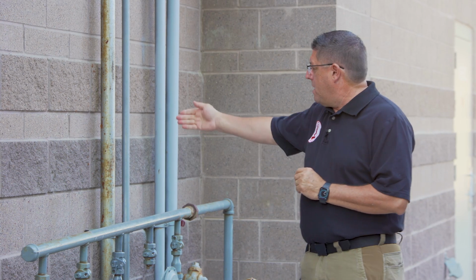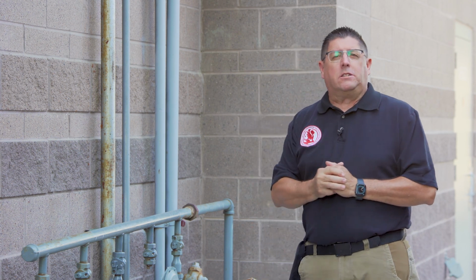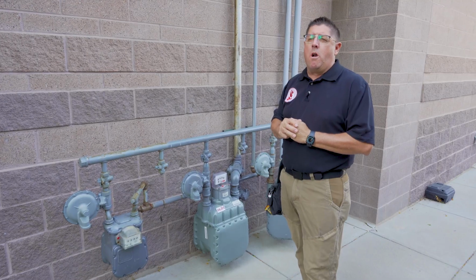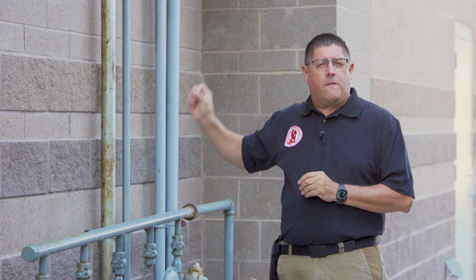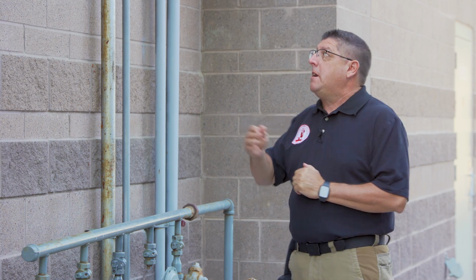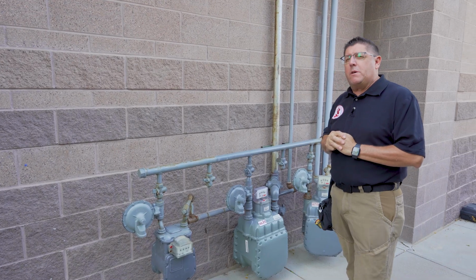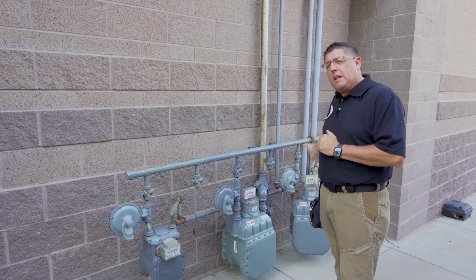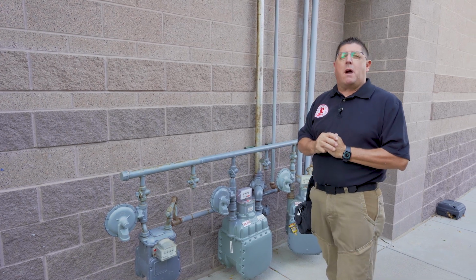Additionally, when looking at gas pipes, we should also have the pipes clearly labeled with some form of marking. The marking is typically yellow, or yellow with black lettering every 5 foot that says gas pipe. In this particular case, the pipes do not have the proper markings. So on my report, I would definitely make note that the meters are not labeled as well as the gas pipe is not labeled. The rest of our heating and venting section will happen up on the roof in this building. So let's head up there.